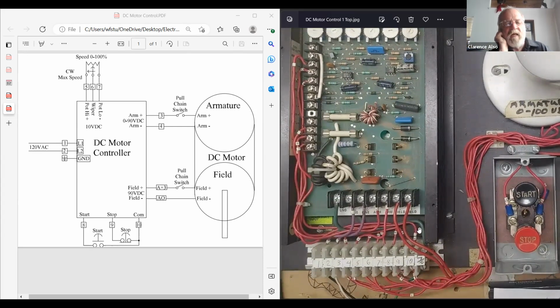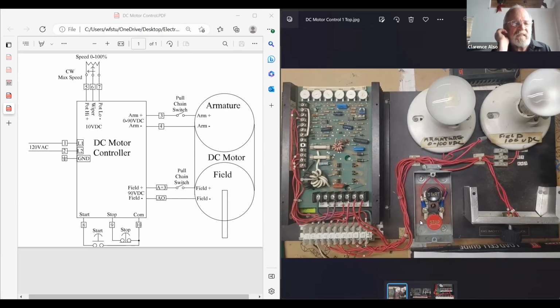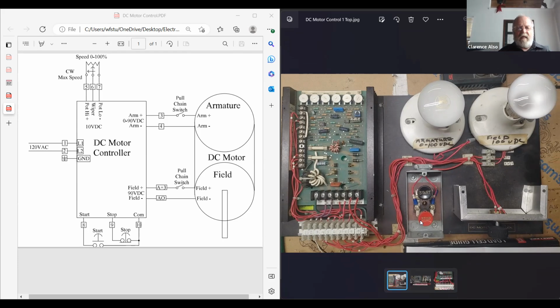So I'm going to pick on, let's go with Nathan first this time. I'm going to say that my symptom is the motor doesn't turn. So basically I hit my start button, I'm expecting the motor to turn. That means if the motor's going to turn, this armature here has to be lit up somewhere.